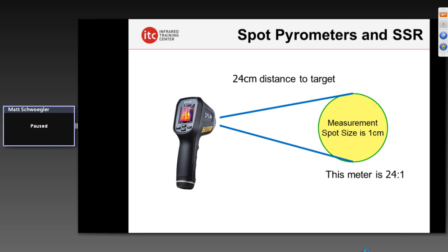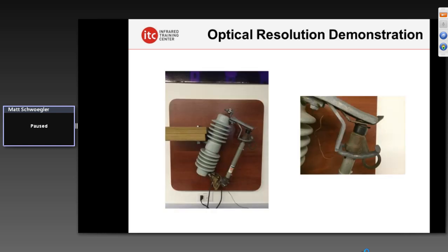This goes down to spot radiometers — in this case an infrared imaging thermometer such as the TG-165 from FLIR. This obviously measures temperature, but at what distance? It depends. This spot meter has what's called a 24-to-1 distance-to-spot size ratio, meaning 24 centimeters away from a target, you're measuring a one-centimeter spot. At two feet you're measuring a one-inch target. But the further you are away, the larger an area you are measuring. Not only do you lose your ability to resolve detail as distance increases, it also affects temperature measurement.